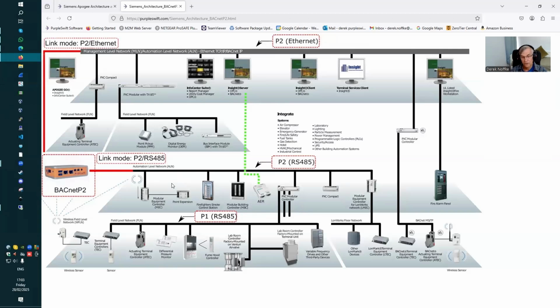And one of the nice things is that it's compatible with the Insight software, which means that you can integrate the site without bringing the site offline, and you can build your new user interface and compare notes with the Insight server. So it makes the engineering much simpler because you're replicating what's on the Insight server, taking it across, and then testing that each page does page for page the same as what the other system does. And when you finish that, you've got the system transferred.